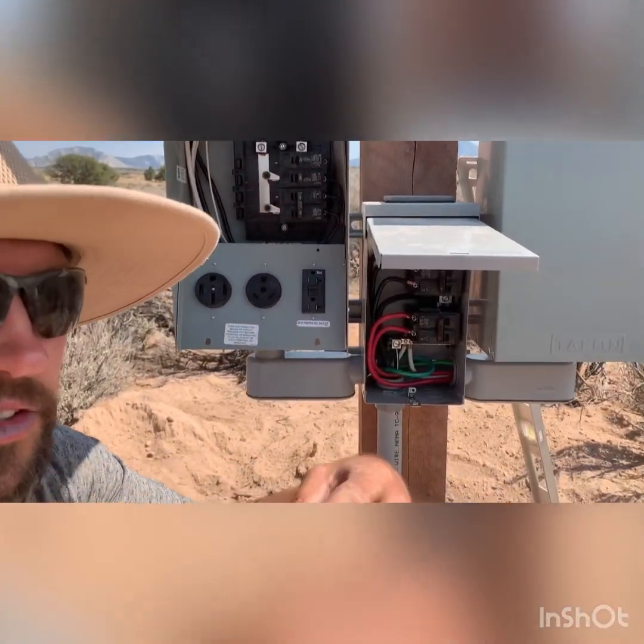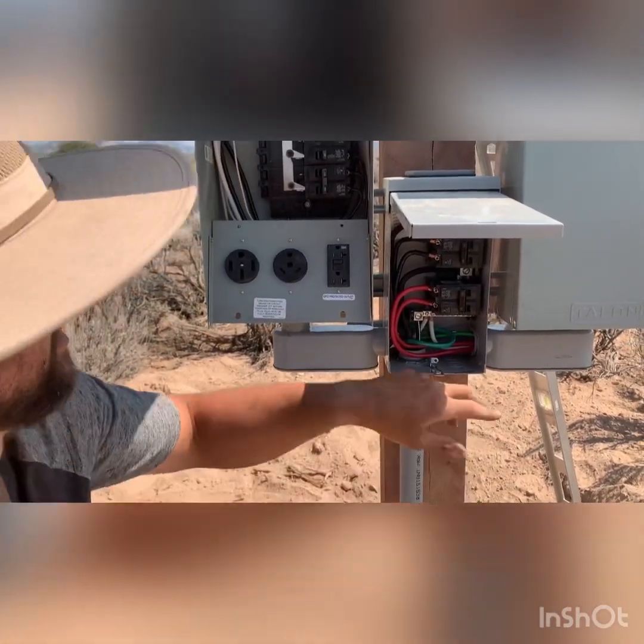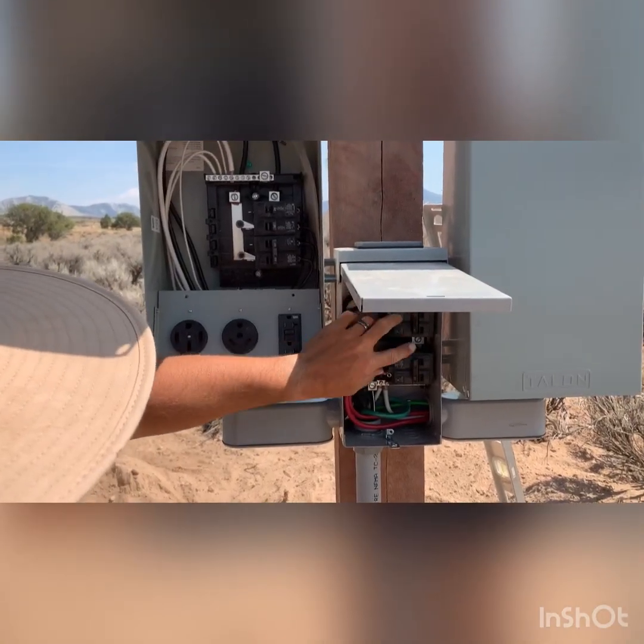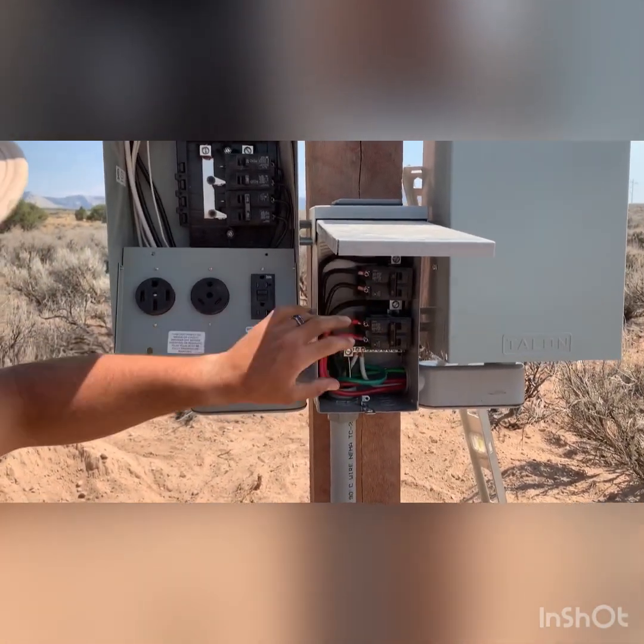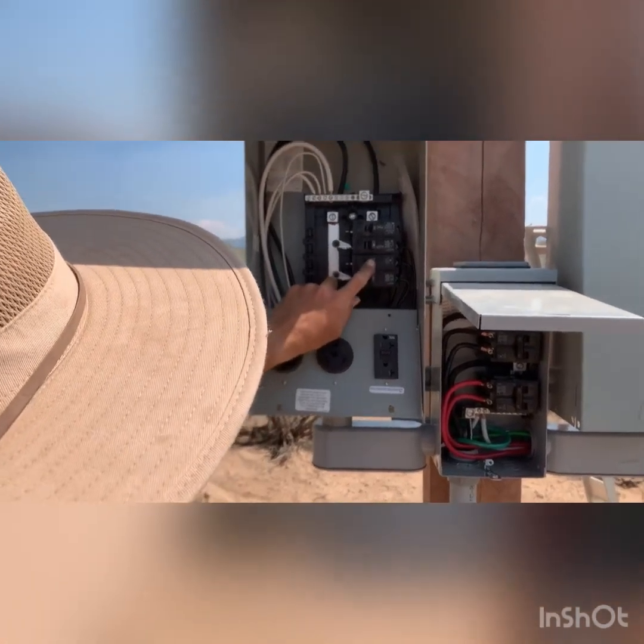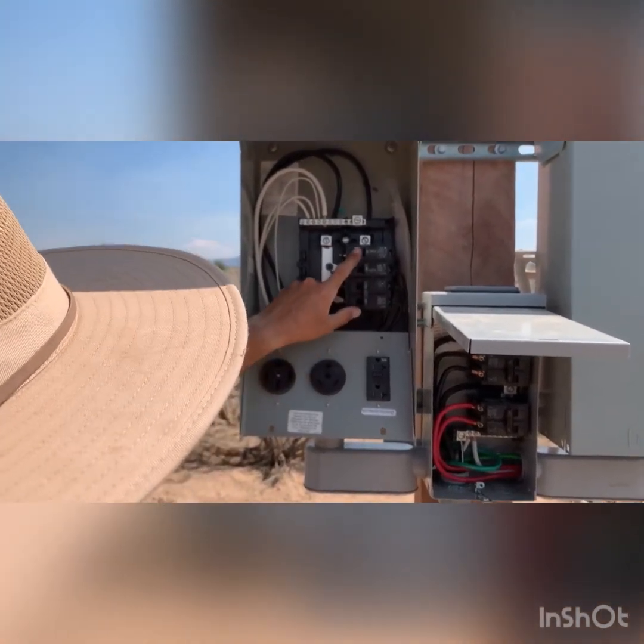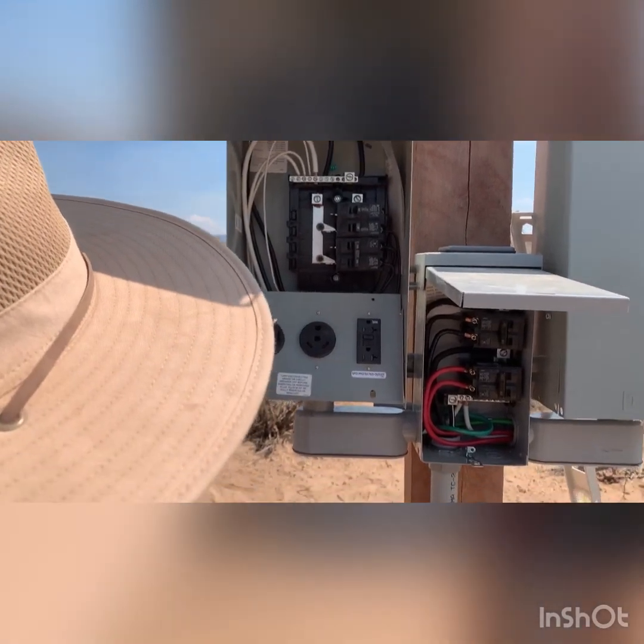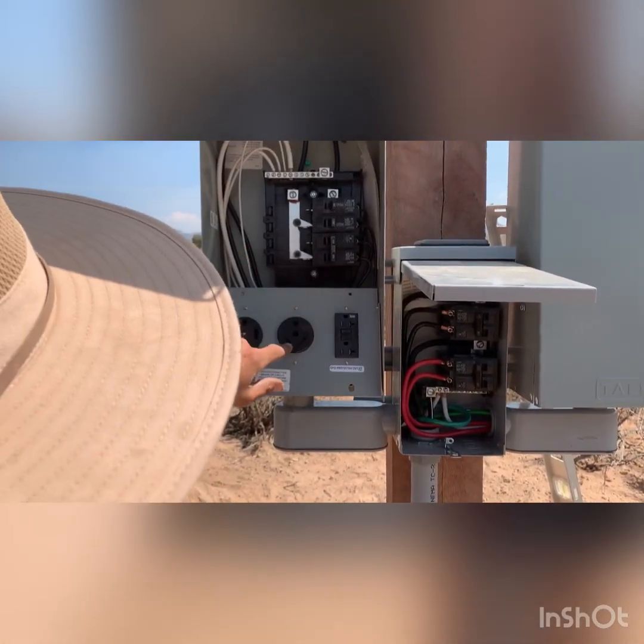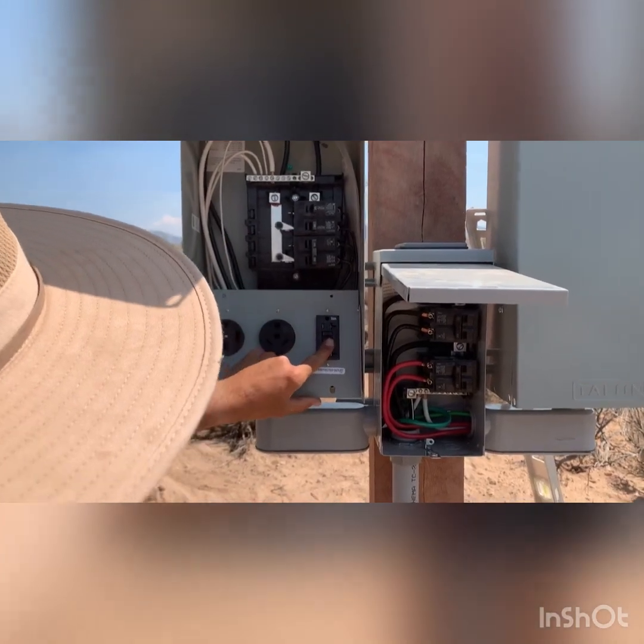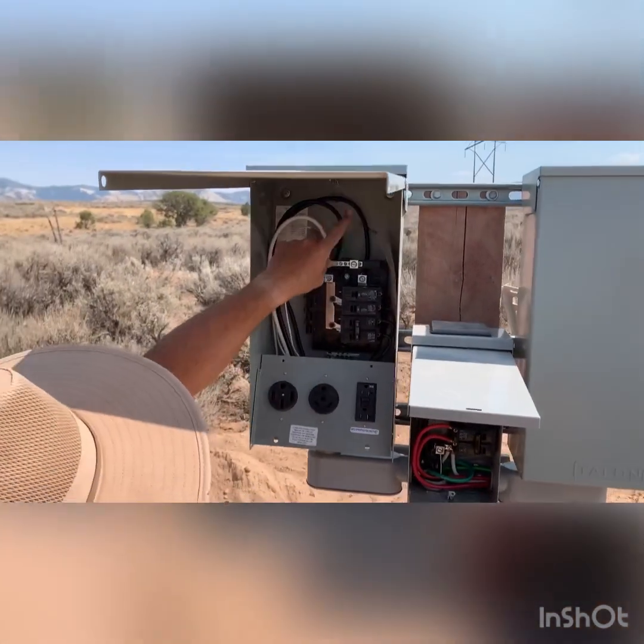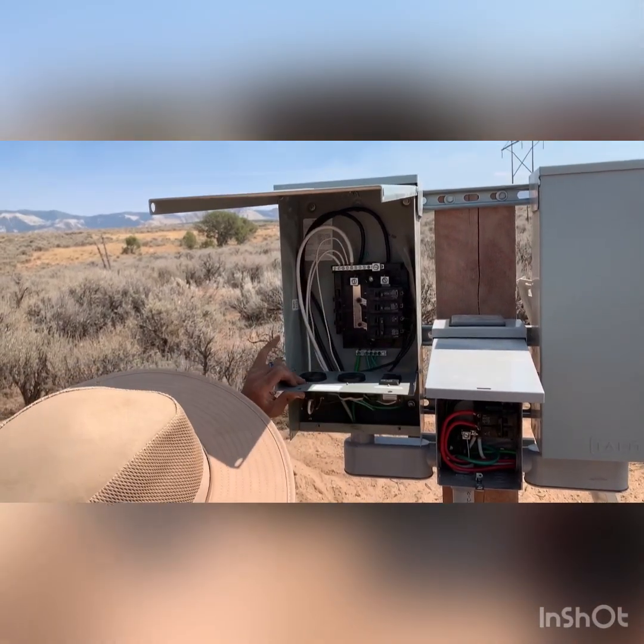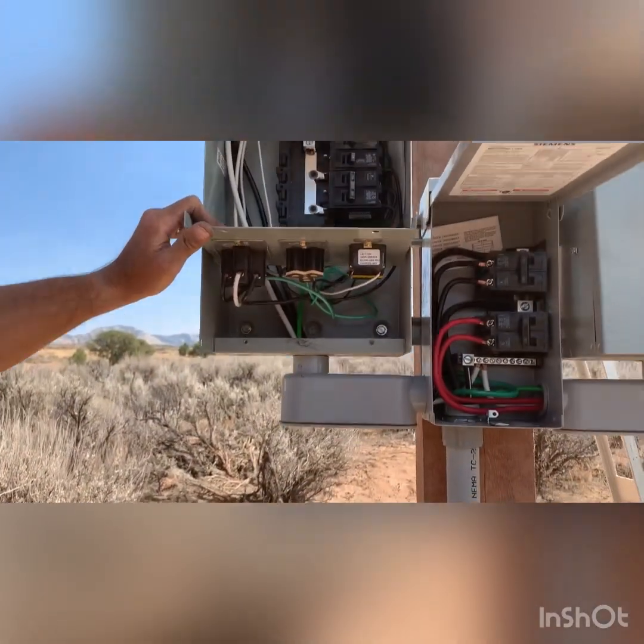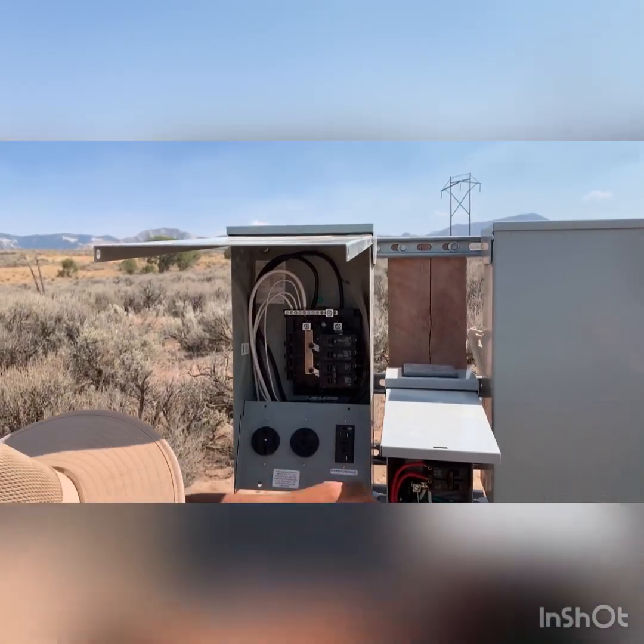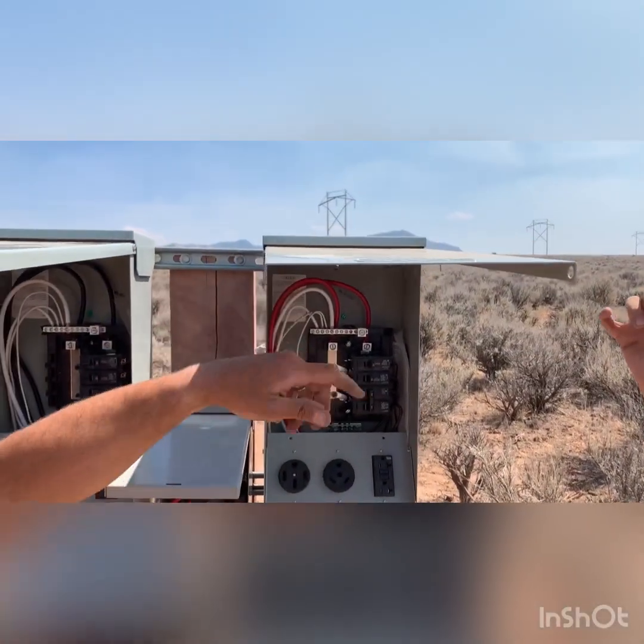So it started at 100 amps over at the main panel. Now we've got a sub panel that divides it into two 60 amp breakers, and then these two 60 amp breakers come over here and divide into a 50 and a 30 and a 20. The 50 amp goes to this outlet, the 30 amp goes to this outlet, and the 20 amp goes to this outlet. And then it's just wired in, and all of this stuff is wired in underneath. And the other panel looks just like this, except it has red hot line instead of black.